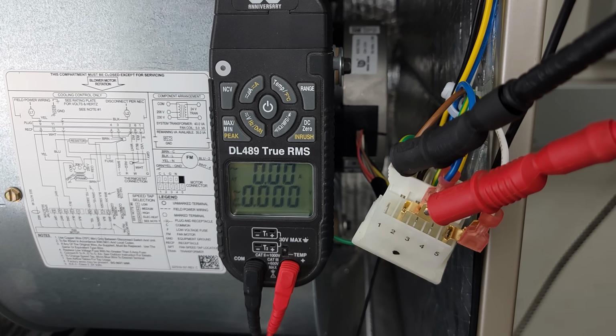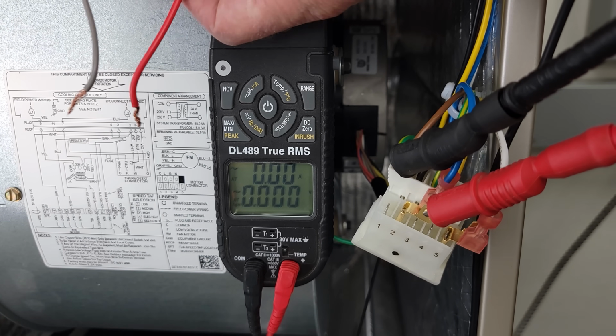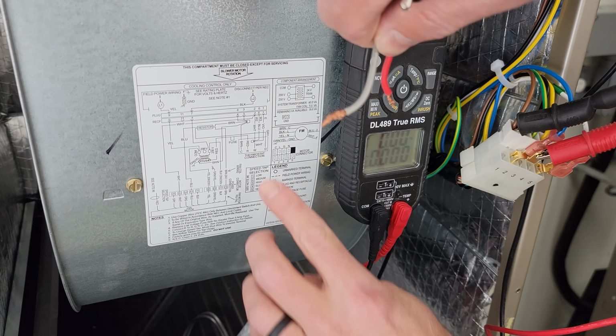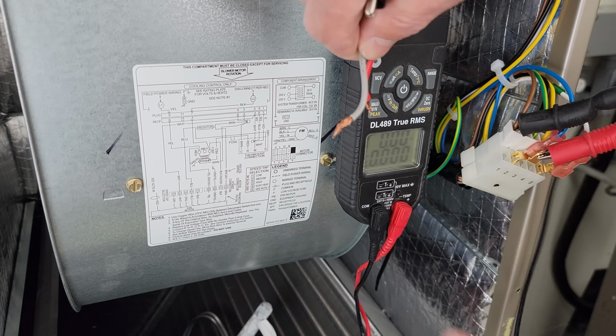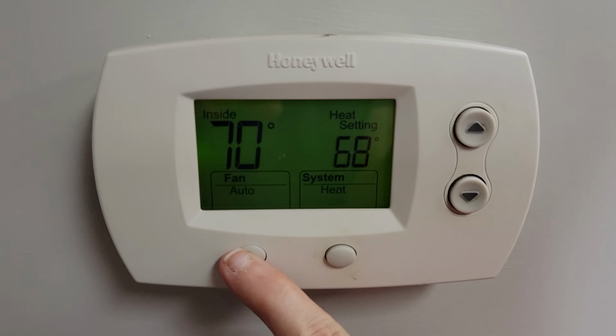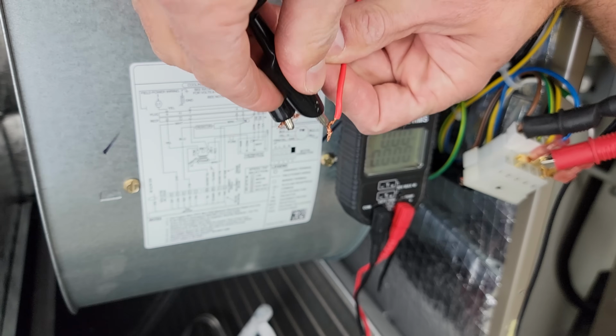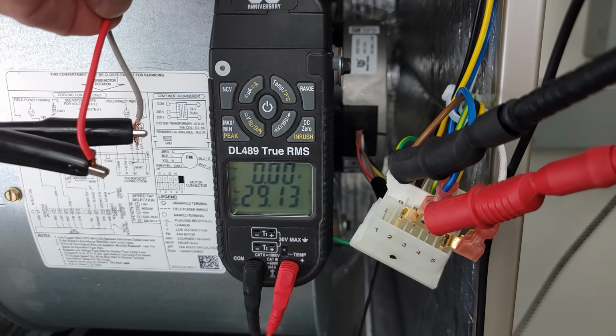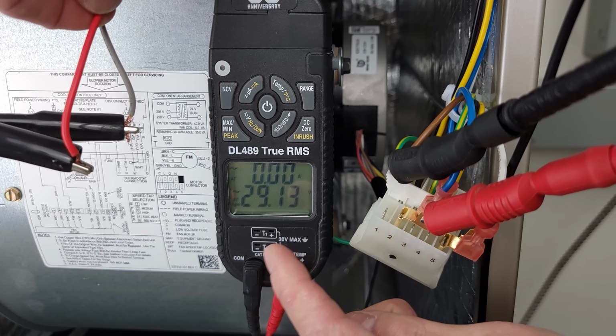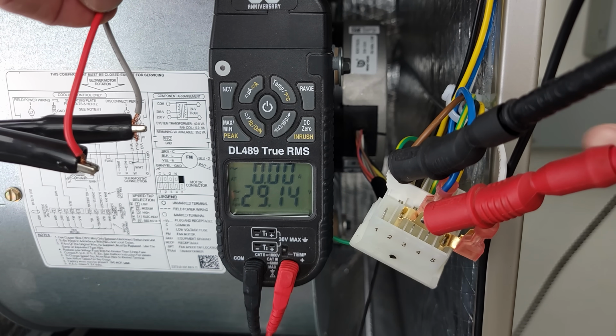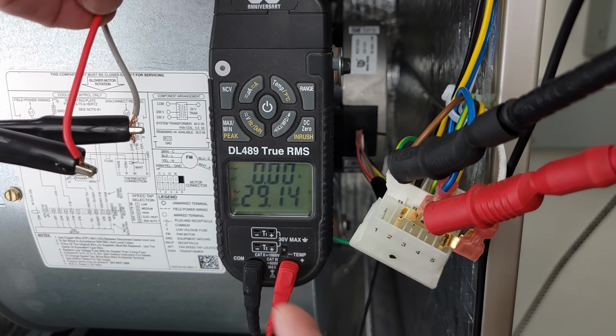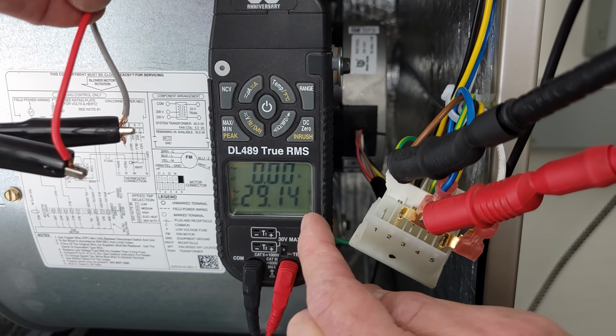Now what we're going to do is we're going to connect our R and G, which are our thermostat wires. And so if you can see right here, R and G, that's going to turn the fan on. And you could just turn the fan on at the thermostat itself, or you can jump the R and the G wires together inside the unit. And you can see now we have 29 volts. If the blower motor does not turn on when you do have high power and 24 volts, you know your blower motor module is bad.